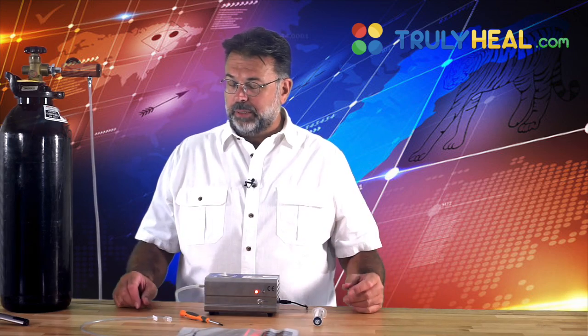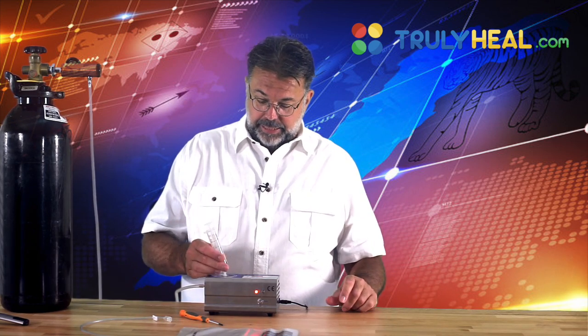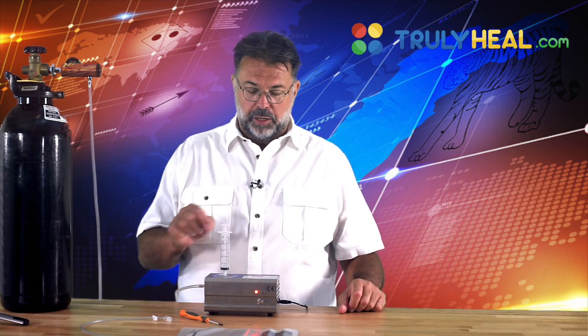Today we're going to look at something very special: how to break the ozone generator and how to fix it. Now, a few of you have created too much pressure within the ozone generator by leaving your syringe on when the oxygen was turned on. Now, I would like to recreate the process and show you.